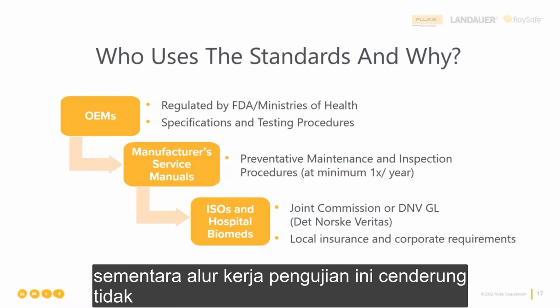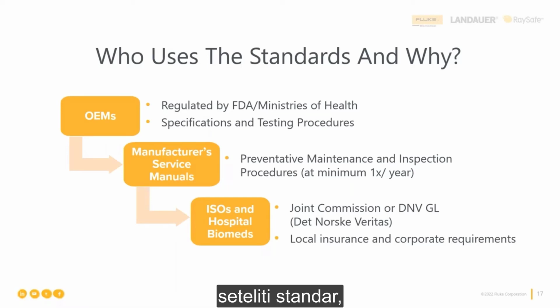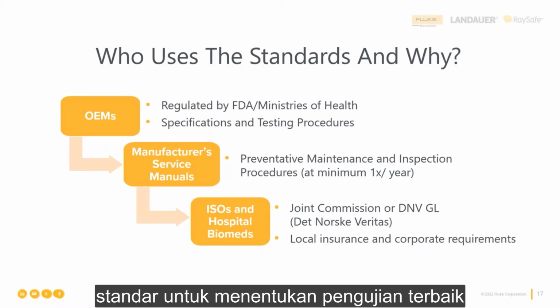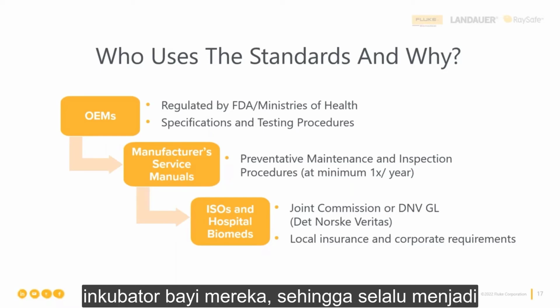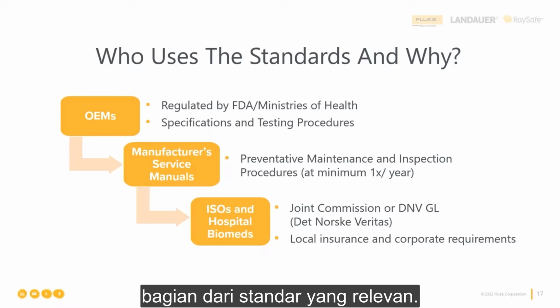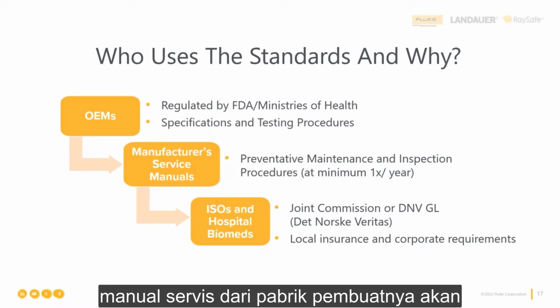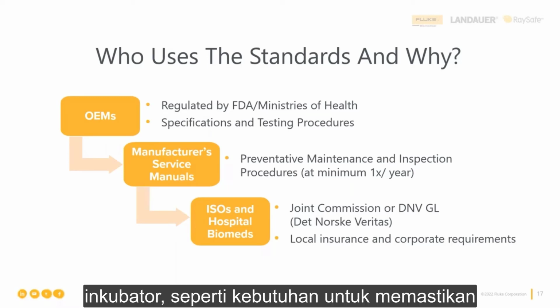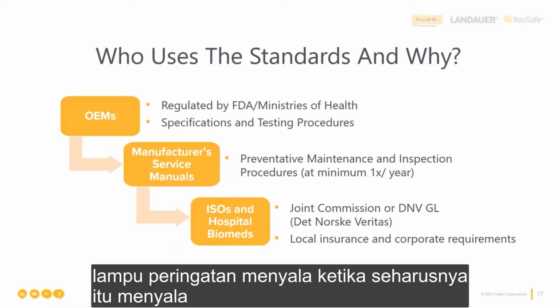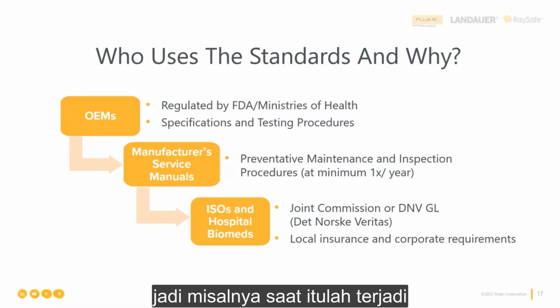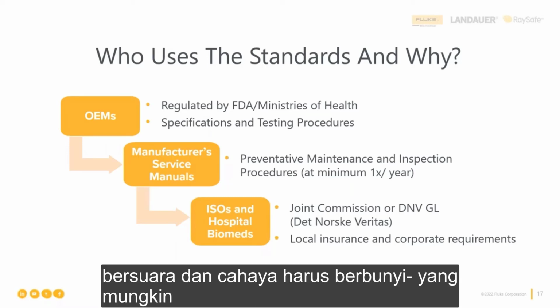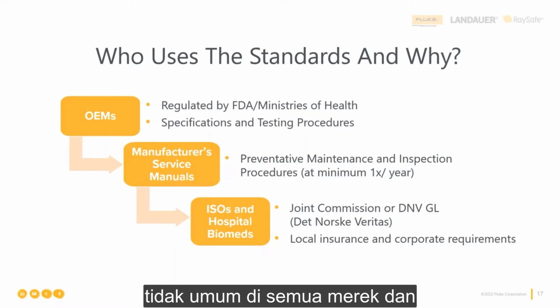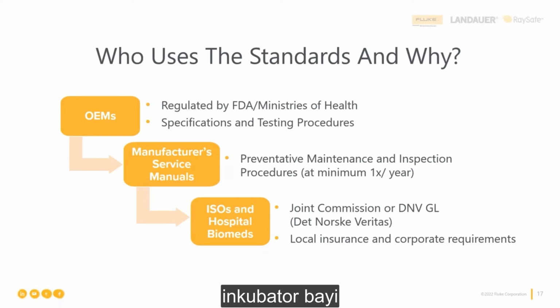While these testing workflows tend not to be quite as thorough as the standards, each manufacturer has applied the standards to determine the best testing for the design of their brand and model of infant incubator. So it's always a subset of the standard that's relevant. The manufacturer's service manual will give model-specific directions to test the incubator, such as the need to ensure warning lights turn on when they should. For example, when the temperature is too high, an alarm should sound and a light should go off. That might not be common across all brands and models of infant incubator.